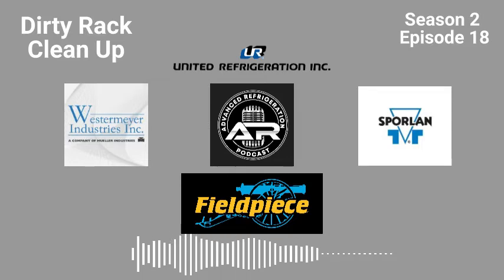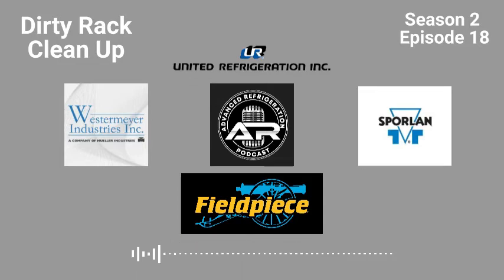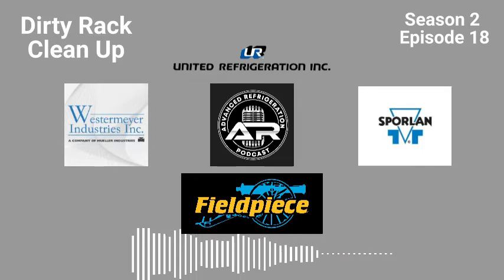But wax is a mineral oil thing. You shouldn't have wax with POE oil. From these burnouts on this rack, there was wax all over the place. It was so severe we actually had a problem with the split, and I personally rebuilt the check valve, and I think 2 or 3 weeks later it failed again. I don't think that's wax though, because I don't think you could have wax in a POE oil system. You could have it in a mineral oil or alkylbenzene oil system. What you're seeing is just gummed up oil.